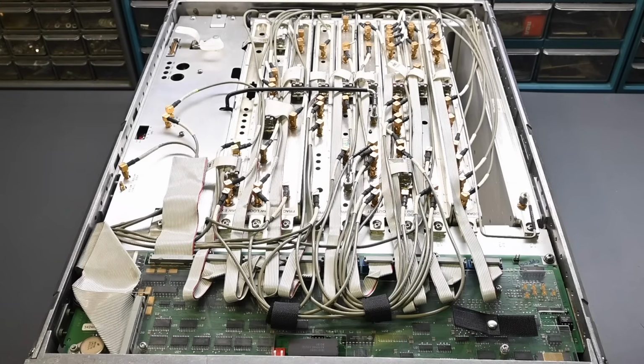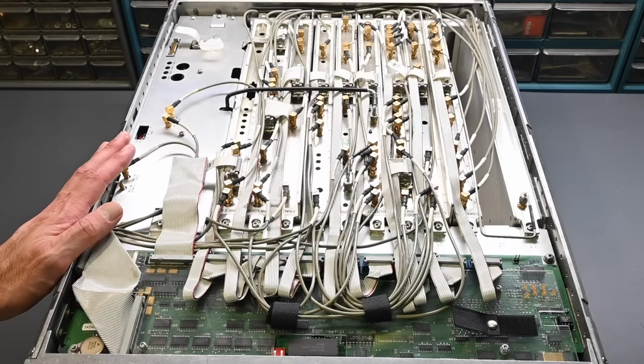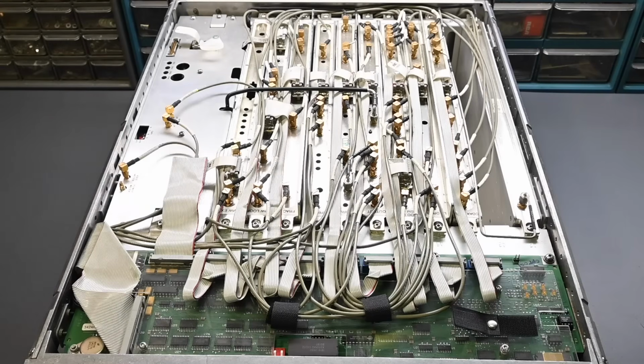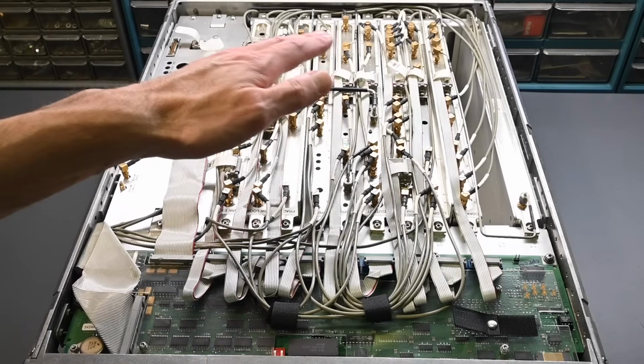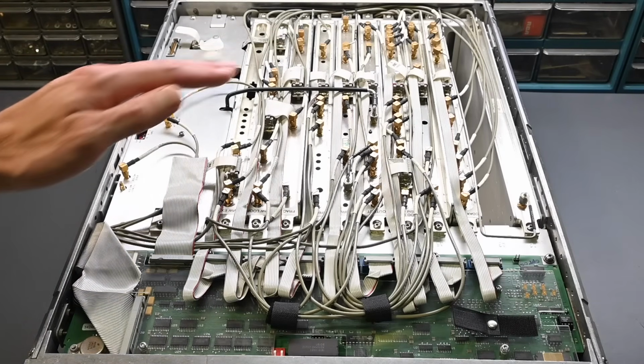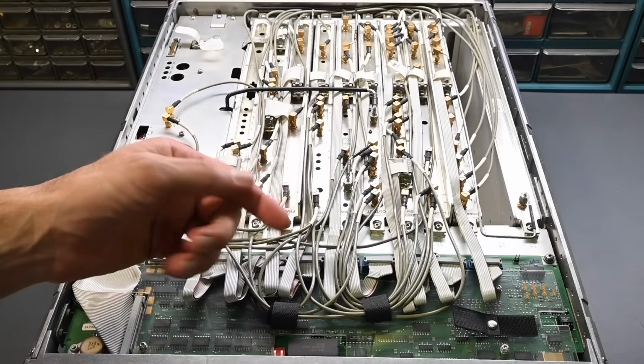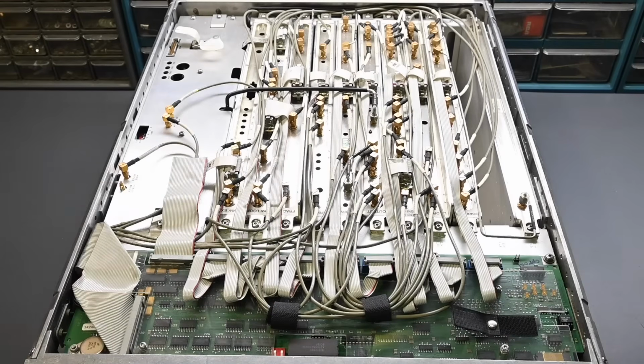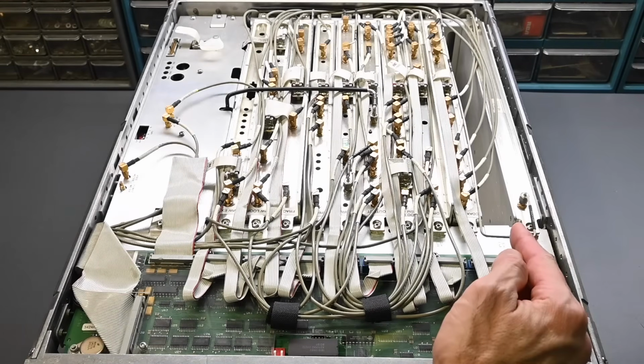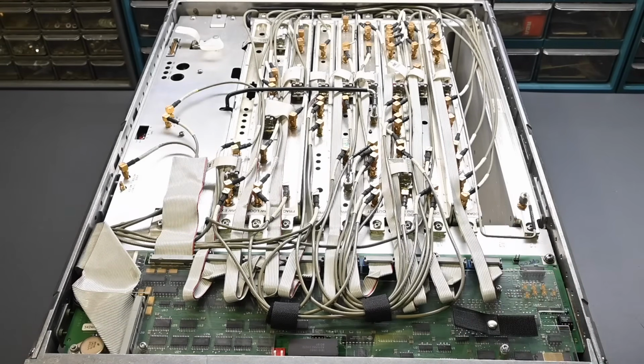All right, top cover is removed, and look at that classic HP quality, so very impressive. So I cleaned out some lint and dust. Most of it was located along that front edge where the vent is in the cover. So the air is drawn through that vent, moves through the instrument, and then exhausts out the back by the fan. And over here you can see it says location A3 and there's an empty slot. So nothing's missing. That location is just not used on this instrument.